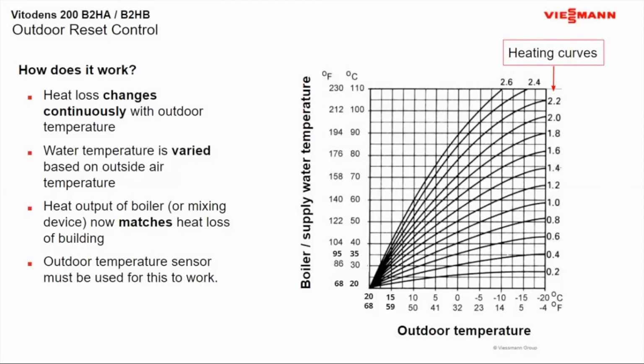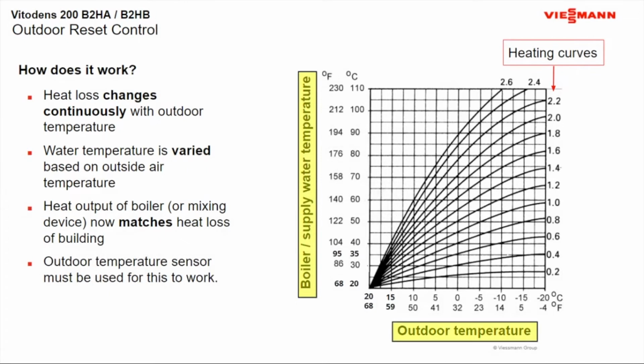So here's a heating curve chart right out of the manual. As you can see, the boiler supply water is on the left-hand side there, and your outdoor temperatures are down at the bottom. When you're looking at this, just be aware that they do have Fahrenheit and Celsius on there, so when you're following a chart, pay attention.